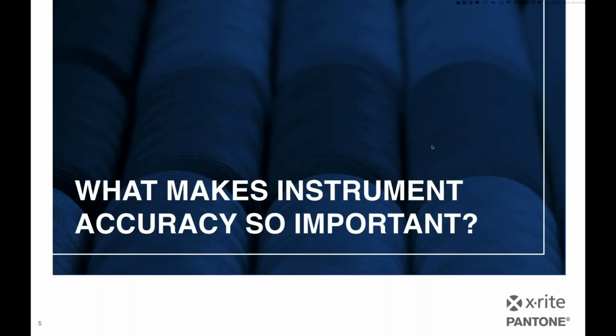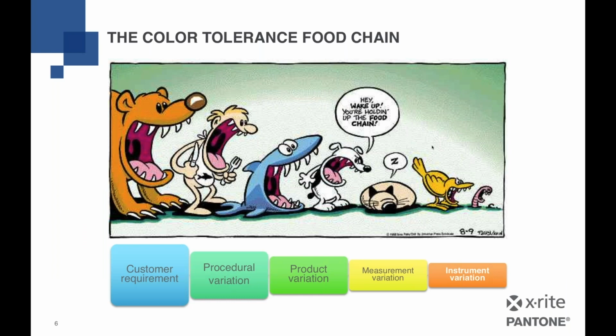So what makes the instrument accuracy so important? Well, it's the color tolerance food chain, in a way, which consists of a customer requirement, which is maybe a color tolerance, which should ideally be larger than your procedural variation, versus your material or raw product variation, versus your measurement variation, and then finally your instrument variation. And that's of course the challenge we have as a spectrophotometer manufacturer: to keep that instrument variation as small as possible, to allow these other tolerances to be subsequently larger.